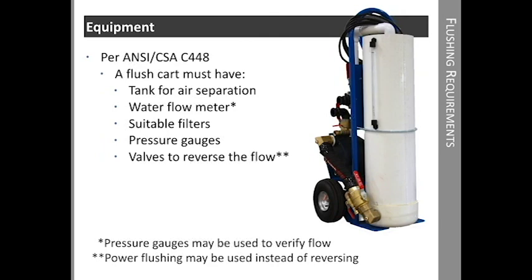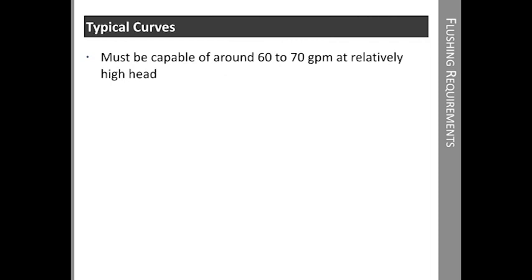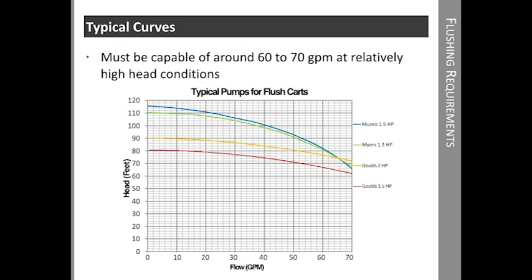In some cases, if the loop is very close to being purged of air, reversing the flow can actually end up being a step backwards. A flush cart should include a pump capable of around 60 to 70 GPM at relatively high head to purge residential and light commercial loops. Depending upon loop design, a flush cart like this can even purge larger loops if valves allow portions of the loop to be purged separately. Here's a chart showing typical one and a half and two horsepower pumps used in the industry. The GeoFlow flush cart uses the Munro pump, which has high head and flow capabilities but can also operate on a 15 amp breaker at 115 volts.